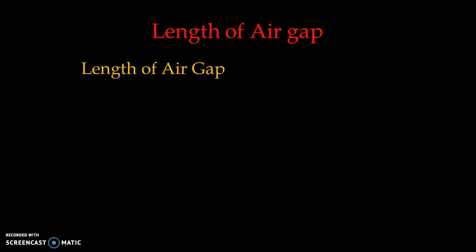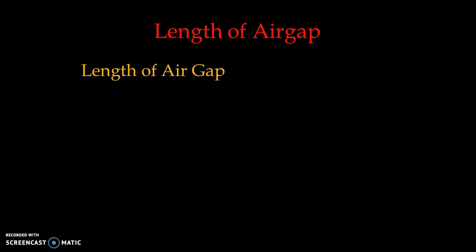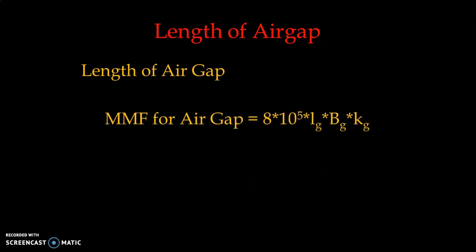We will now discuss how to estimate the length of the air gap. Length of air gap: we have one relationship that is LG/τ, which can normally be taken as 0.02 to 0.025. Based on this ratio, we can easily estimate our length of air gap. But there is another possibility — we can find out a more accurate estimate of the length of the air gap.